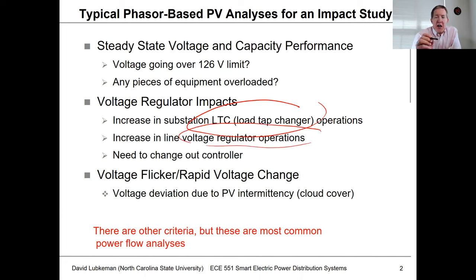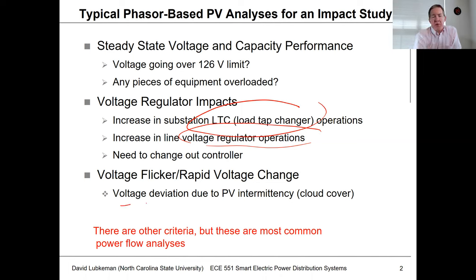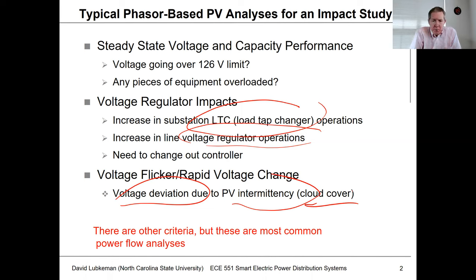We're also worried about impacts on existing equipment like voltage line regulators, especially at the substation. At the substation you'll have a top-of-feeder regulation device, which is fairly expensive. You want to make sure you're not putting increased wear and tear on this device, because it would be very costly to fix or replace. Replacing a line voltage regulator could cost $80,000 to $100,000. We also consider voltage flicker and rapid voltage change due to PV intermittency linked to cloud cover.